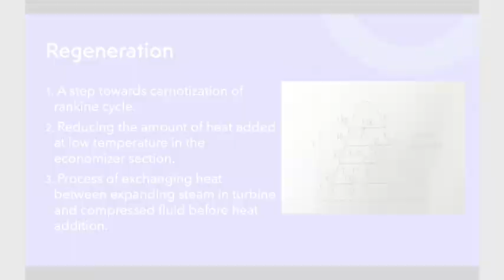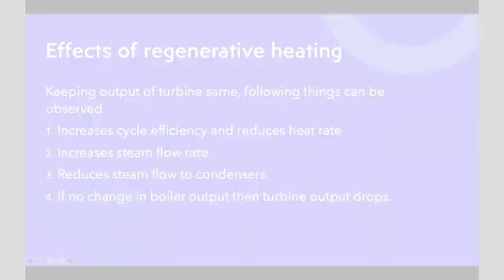Now, to understand this phenomenon of regeneration in summarized form, let me present you with an example. Suppose my unit is running at 200 megawatt. The coal input into the boiler is 150 tons. The steam flow is 600 tons and the vacuum is 660 mm of Hg. And presently the heaters are out of service. If I take heaters into service, my coal input would remain 150 tons. My steam output will increase to 700 tons. My vacuum will increase to 665 or 667 mmHg, and my unit load will increase to 202 megawatt. Therefore, with regeneration, I require a little bit higher boiler size and a little bit smaller condenser size.